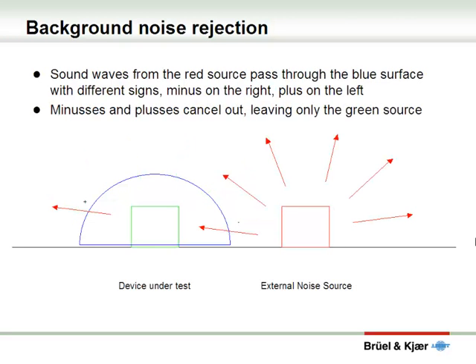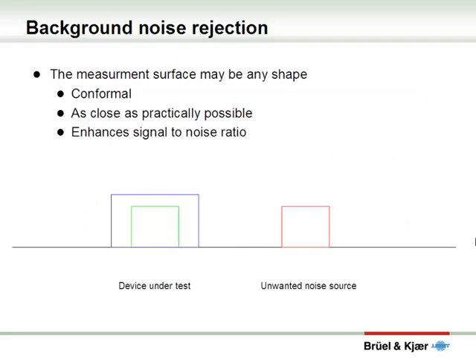Next, we'll have a look at the external noise source. The external noise source is radiating sound waves of its own — those are the red arrows. They will pass into the blue measurement surface with different signs depending on which side. As the sound waves enter the blue hemisphere, they have a minus sign, and as they leave, they have a plus sign. So integrating over the blue surface, the minuses and the pluses will cancel out, and the influence of the external noise source is cancelled. When determining the sound power of the green box, the blue measurement surface may be of any shape that's convenient. For practical measurements, it's often best to have the blue box as close to the green source as possible. This will enhance the ratio of the sound you're measuring to the background noise and keep your measurements clean.